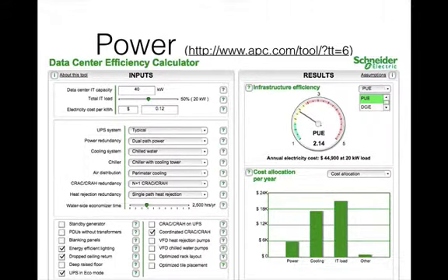As regarding the power, it is estimated that each rack is rated at 2.4 kilovolt amp, and with the 20 racks total, there are about 48 kilovolt amp rating, and the entire power for the data center should draw around 40 kilowatt. Using the data center efficiency calculator found here, I expect a PUE of over 2 and annual costs of electricity over $44,000.